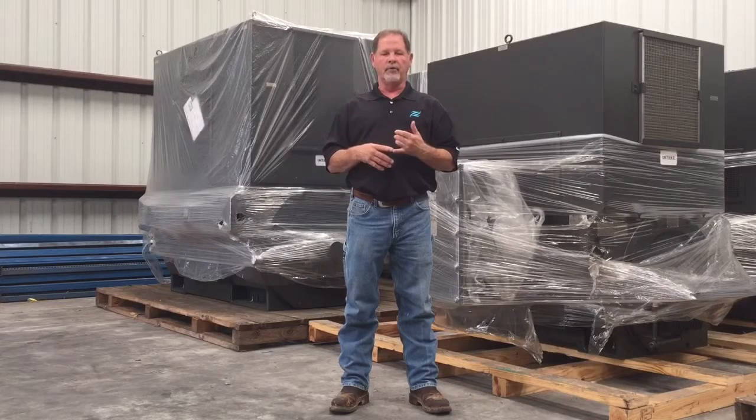When you get in the field before programming, there are several things you need to know ahead of time. The FLA, that stands for the full load amps of the motor. Know what that is at 460 volt or 230 volt, whichever voltage you're running. Second of all, you need to know the horsepower and the RPM. Next, we will go into the programming of the VFD.